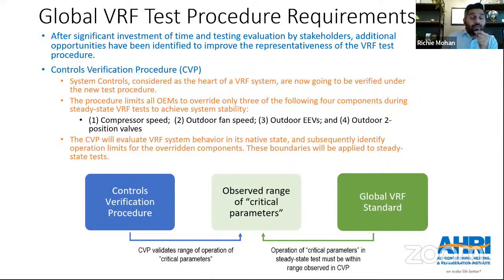Now, we had a lot of discussion. We in fact looked at the entire refrigeration cycle to see which parameters are going to be the most important and critical for the purpose of CVP. And we came to these 4 because we realized that the other parameters, even though they might be critical, may be indirectly impacted when we modulate any of these 4. And beyond that, we also realized that the other parameters are best left free floating, because their impact on the overall efficiency and performance of the product may not be as much.